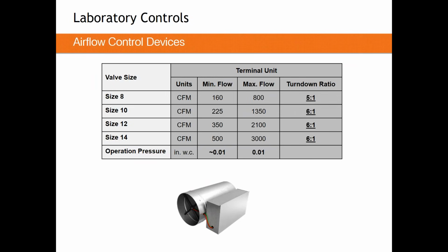So how do these devices actually line up as far as pressure and airflow and performance goes? Again, for a terminal unit, there's no claimed accuracy for these devices. You might see from some manufacturers that their transducer has a certain accuracy, or their box has a certain accuracy, or the sensor that captures that airflow has an accuracy. But when you build these all together, nobody's going to claim any one set accuracy for these devices. So we really can't give you that number, but we can tell you the minimum pressure drop you need to push airflow through that device.